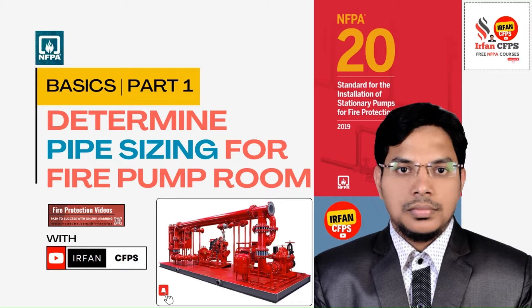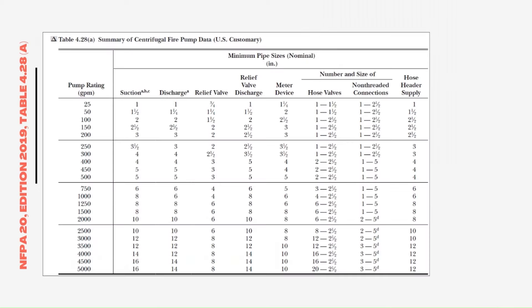In today's class we are going to determine the pipe sizing for the fire pump room. We can find Table 4.28 in NFPA 20, from which we can determine the minimum pipe sizes based on the fire pump capacity. We shall discuss this table in detail in our next slide.